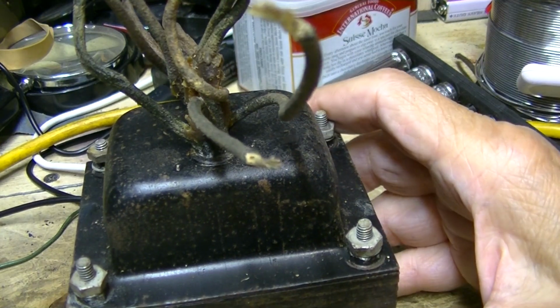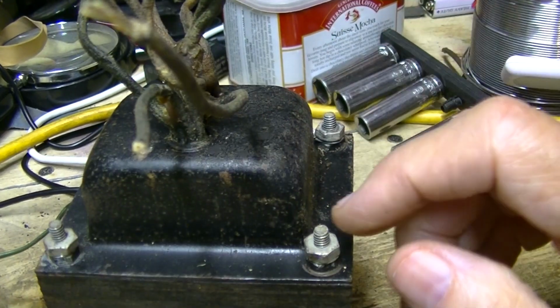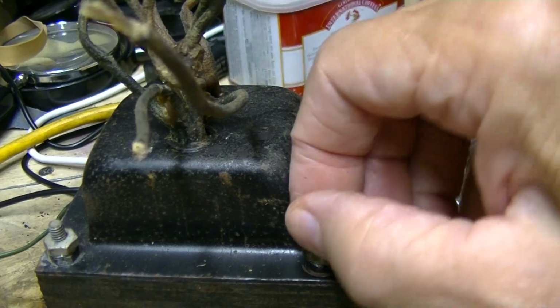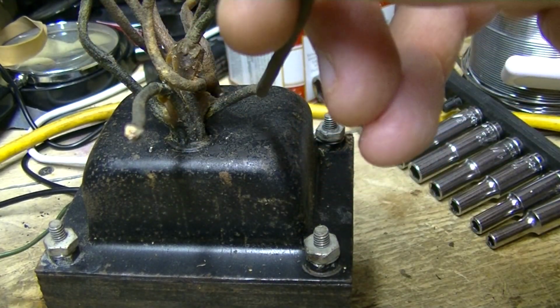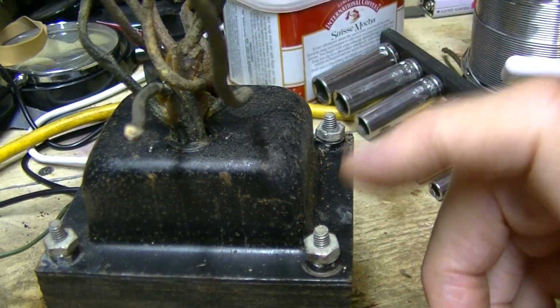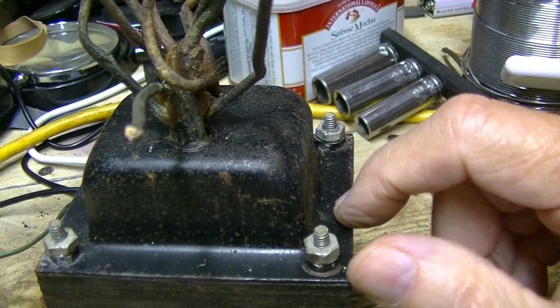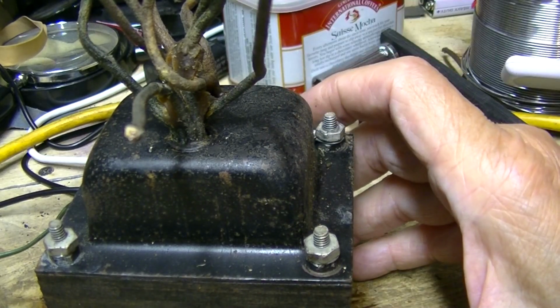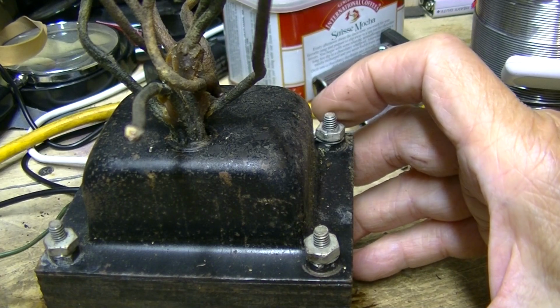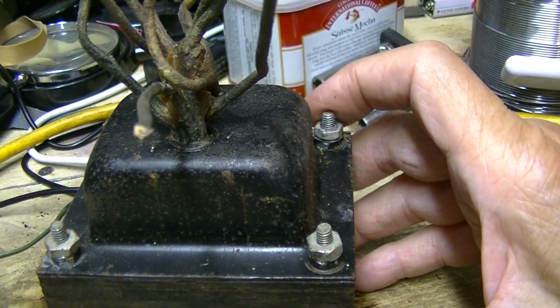...is put my ohm meter on one of these here and test the resistance, if any, between a winding and the transformer shell. If there is a breakdown there, we're in trouble.